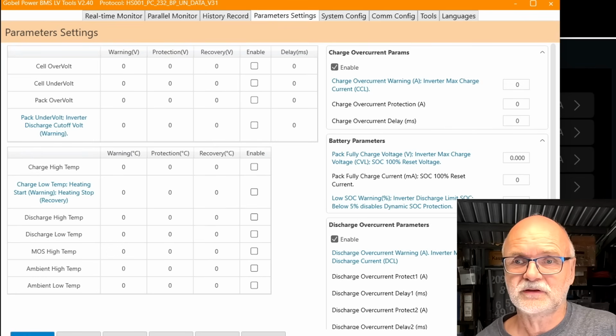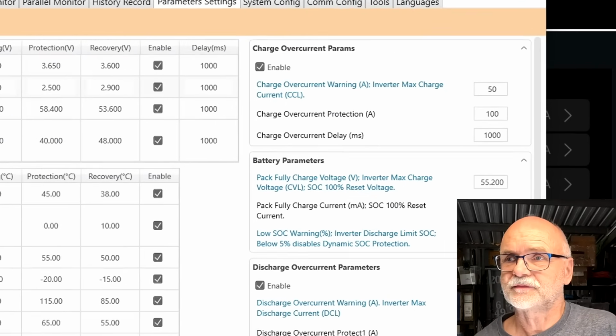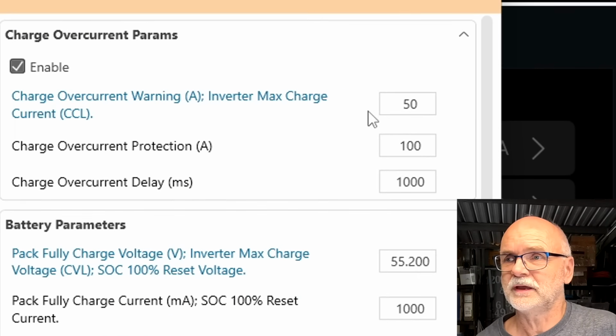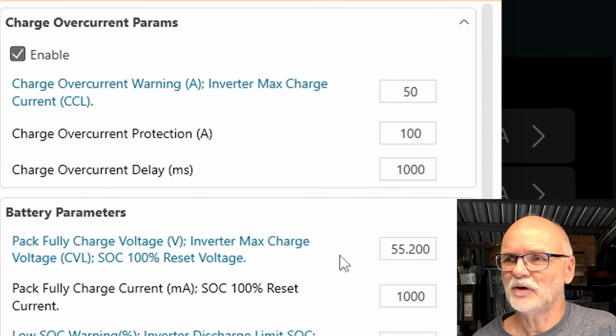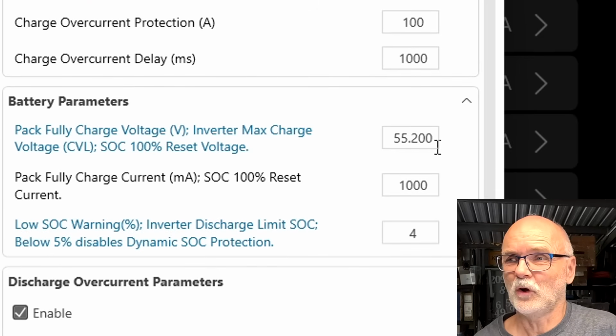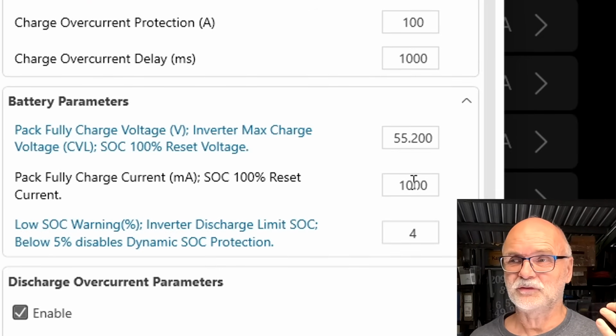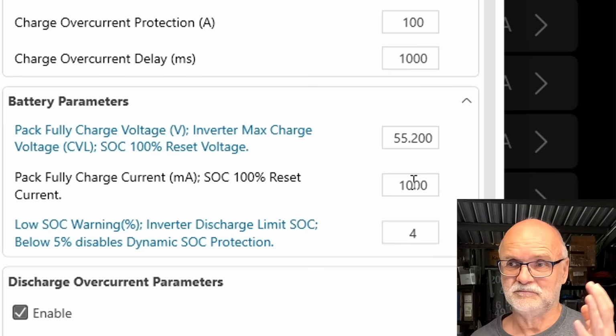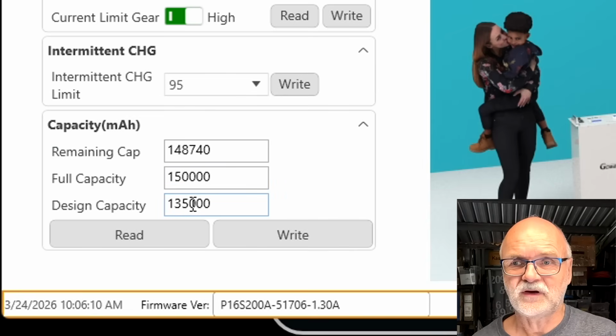We go to read. All right, so overcurrent warning, which is our CCL, doesn't matter. Important is 55.2 volts, maximum charge voltage. Then we wait until the current goes under 1 amp, and this resets your BMS to 100% then. Perfect. 135 ampere hours, full capacity, 150.